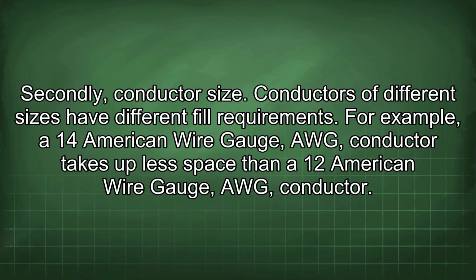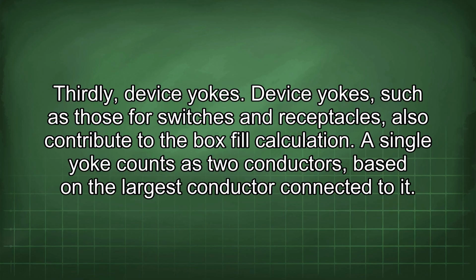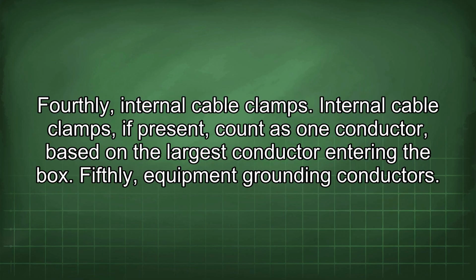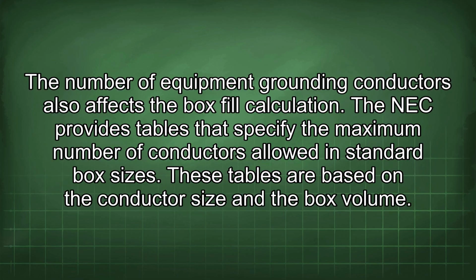Secondly, conductor size. Conductors of different sizes have different fill requirements. For example, a 14 American wire gauge (AWG) conductor takes up less space than a 12 AWG conductor. Thirdly, device yokes. Device yokes, such as those for switches and receptacles, also contribute to the box fill calculation. A single yoke counts as 2 conductors based on the largest conductor connected to it. Fourthly, internal cable clamps. Internal cable clamps, if present, count as 1 conductor based on the largest conductor entering the box. Fifthly, equipment grounding conductors. The number of equipment grounding conductors also affects the box fill calculation.